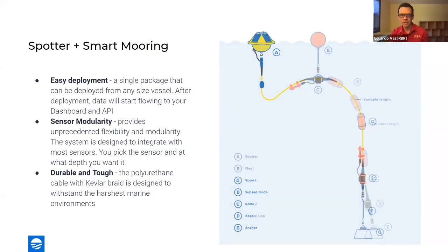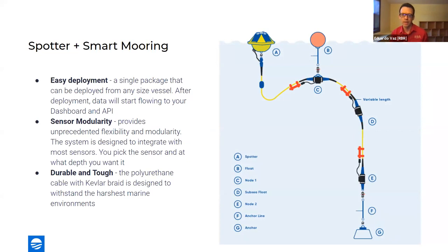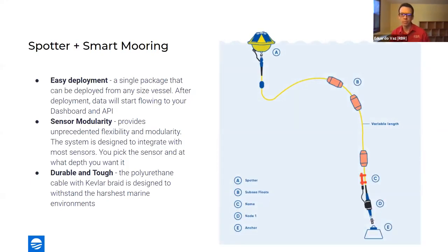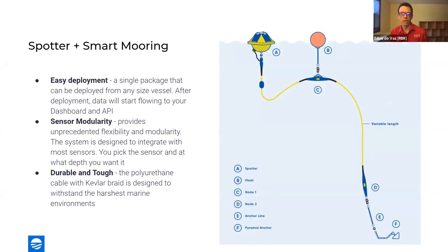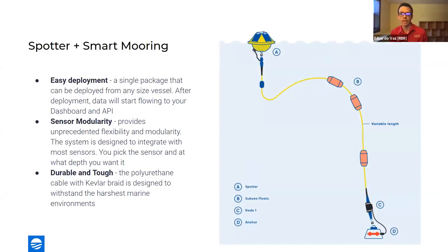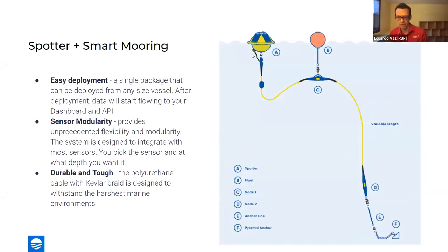I was going to say something regarding Kevin's question as well. It drifts a little bit away from what the smart mooring is doing, but you can reach directly out to us if you want, and we can maybe help a little. We generally provide the mooring line modem with some systems that already have RBR instrumentation in it, but we do integrate some ADCPs, and again, you do need a jacketed mooring line, but in that case we have a limit of 4,000 meters. So it may be applicable depending on what other instruments could come in. If you want to send a note, I can provide my email as a direct message to you.